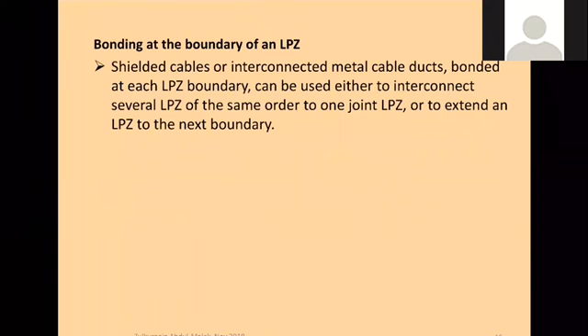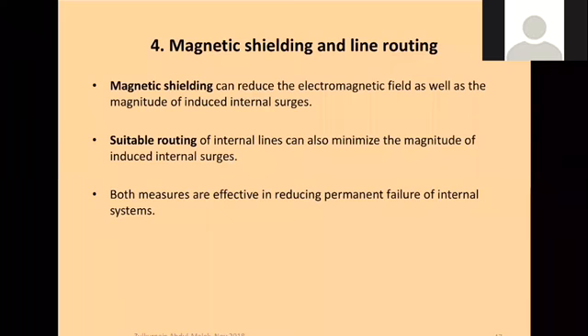So the summary is, we need bonding bars. If you have a multi-story building, at each level we have bonding bars to which we connect all the service lines as well as our electrical lines and signal lines, to make sure equipotentialization is achieved when there is, for example, a lightning strike, where the earth potential goes up and all the bonding bars will go up as well, and all the systems will go up in terms of voltage. So we need to bond them properly. Now, we have SPDs: some are bonded directly to the bar, some through SPD.